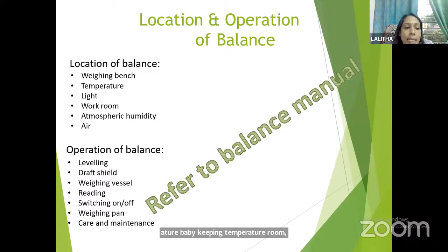Okay, the next is the location and operation of the balance. The important thing is where we keep the balance. Now I'm going to give some tips on how to place our balance. Normally in all labs, this is a standard lab. Normally we will choose the place where we keep all the standards together. So the weighing bench, the room temperature where we keep the balance, the light, the workroom, the atmosphere, humidity, and the air. As for operation of the balance: leveling, draft shield, weighing vessel, reading, switching on and off, weighing pan, care and maintenance. All this we can refer to in the balance manual.